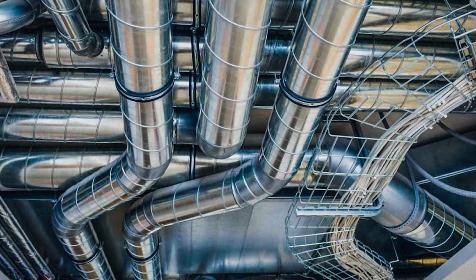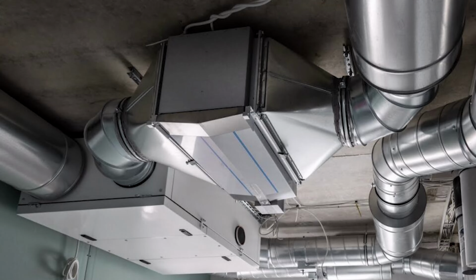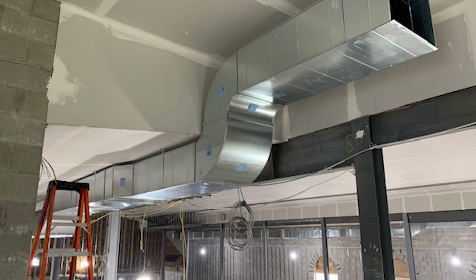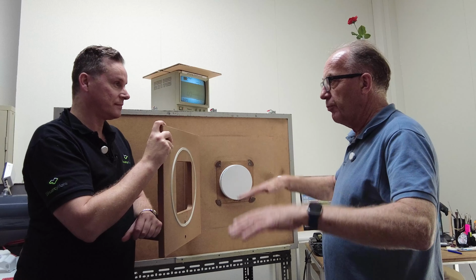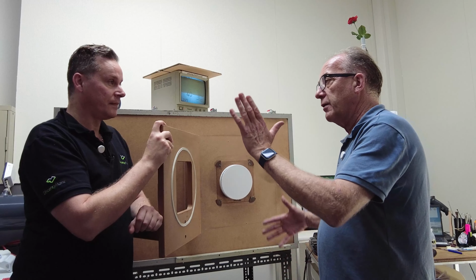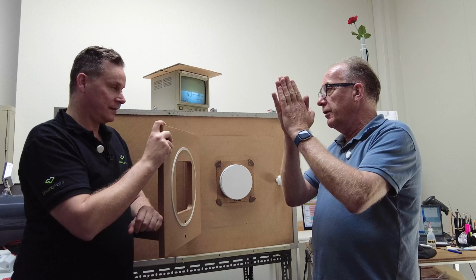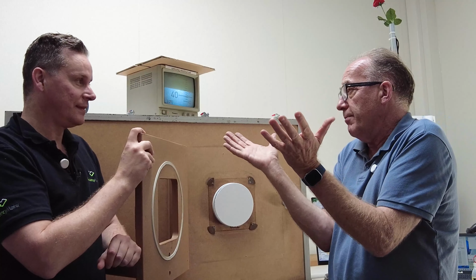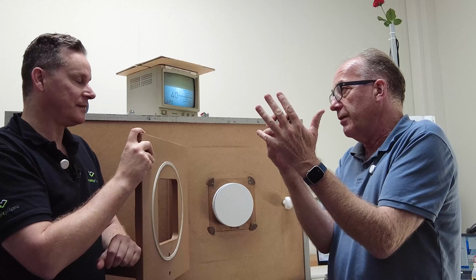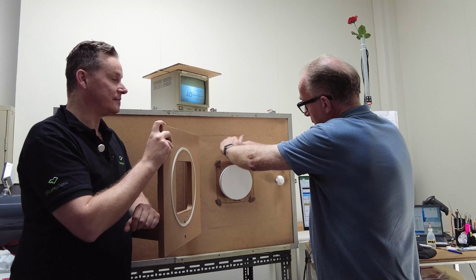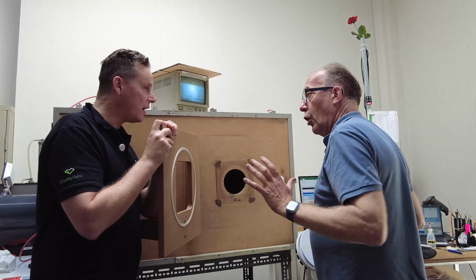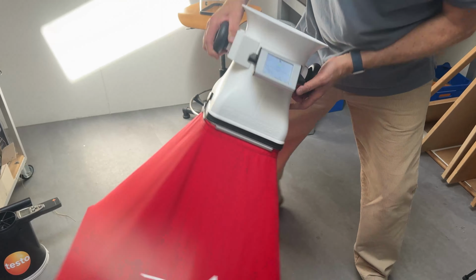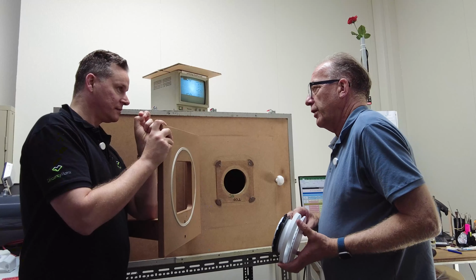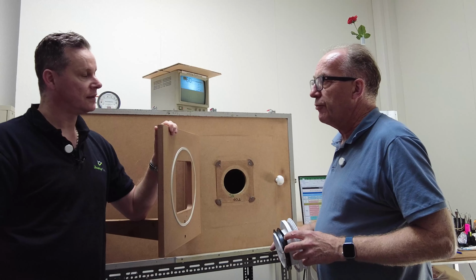A normal flow hood does a good job on many systems, but you never know where and when the deviations are. And then there's another problem. If you have a supply exhaust system, then the supply is more difficult to measure than the exhaust. It has to do with the fact that with exhaust, the flow comes in the back of the measuring unit of the instrument, and that's always the same. The flow pattern coming from the back is always the same. But with supply, it comes out of a grill like this, or out of a hole, and those are all different flow patterns. Your instrument has to account for that in a way. The Flowfinder has a grill that breaks up the flow and then starts compensating, so it's not so much influenced by the flow pattern.